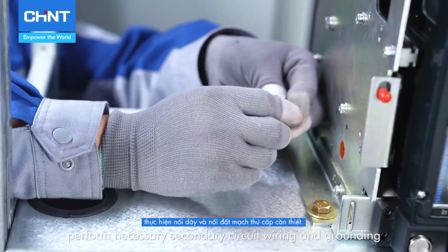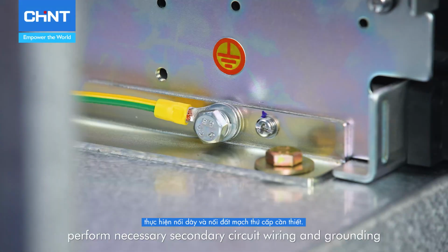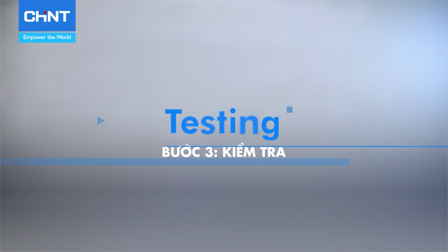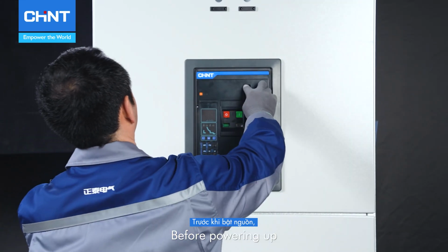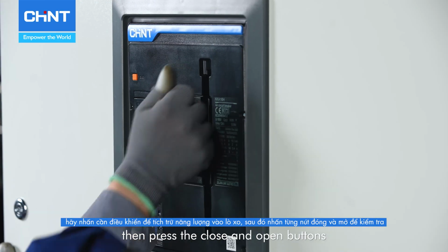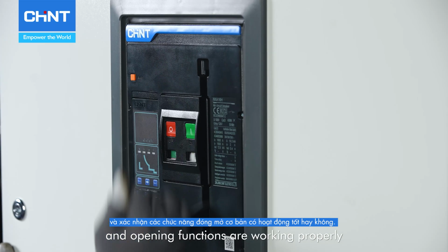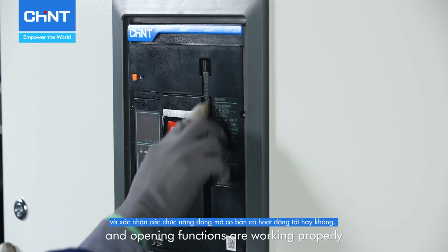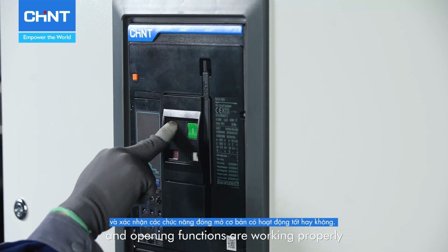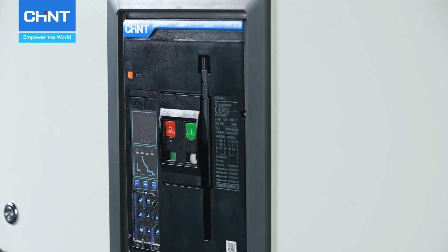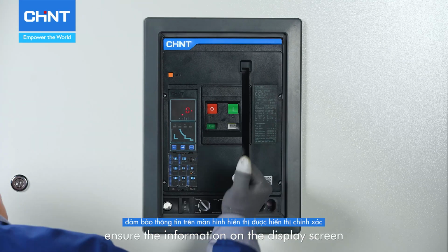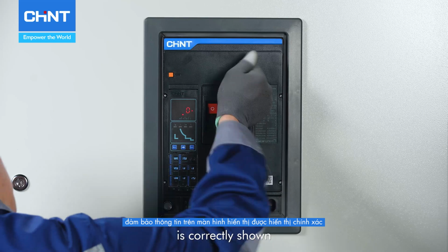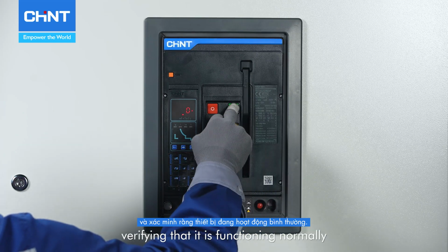Lastly, perform necessary secondary circuit wiring and grounding. Before powering up, press the handle lever to store energy in the springs, then press the close and open buttons separately to test and confirm that the basic closing and opening functions are working properly. After powering up, ensure the information on the display screen is correctly shown, verifying that it is functioning normally.